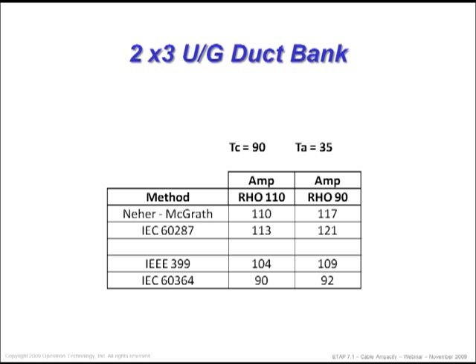Here I'm giving a comparison of four methods, but let's look at the first two: thermal calculations based on Neher-McGrath and IEC 60287. When you look at these two standards they're pretty much very close to each other, but there are still differences. We ran it for a soil thermal resistance (rho) of 110 and another at rho of 90, conductor temperature 90°C, ambient 35°C. You can see IEC gives more current — Neher-McGrath is about two to three percent more conservative than IEC for this particular cable and installation.